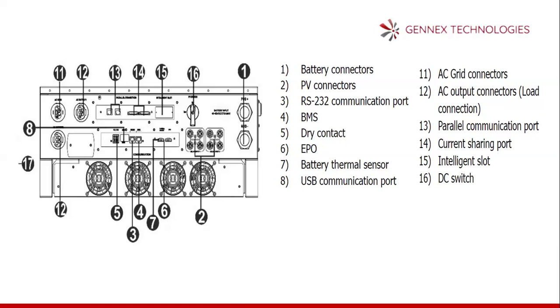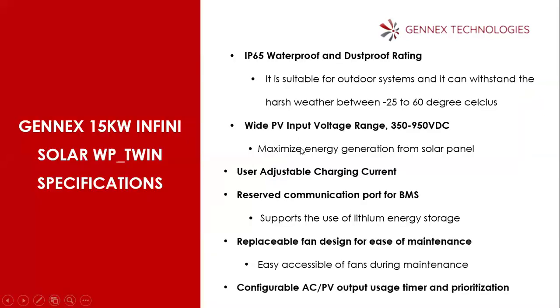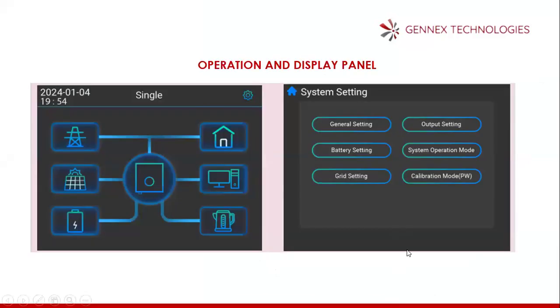Then the fans are at the outside of the inverter. The inverter is actually IP65, which makes it very durable and an outdoor unit. So in order to do a maintenance, maybe a small maintenance you want to do, the fans are outside. It is accessible. You can just remove it, clean it and return it back without opening any part of the inverter. Okay, this is the screen layout. This is the screen layout, which shows the grid, solar panel, battery, the load you're powering, then how you can access the settings.